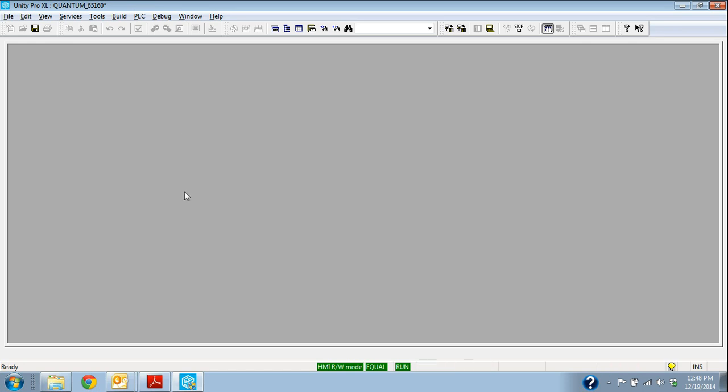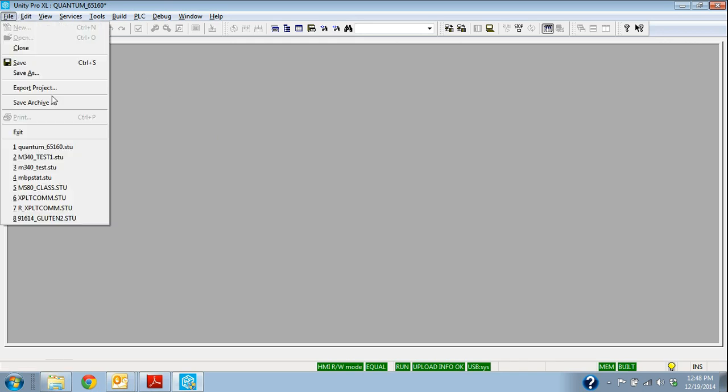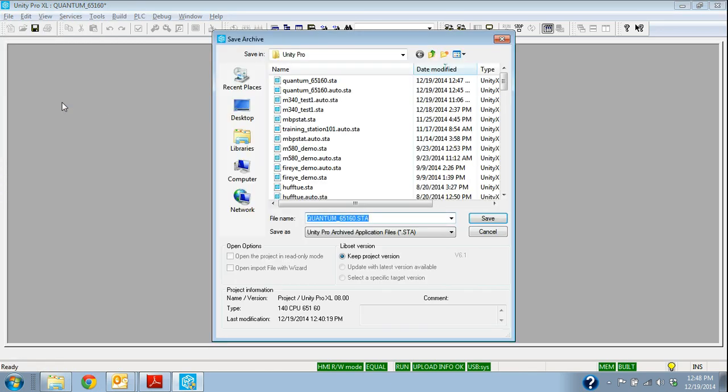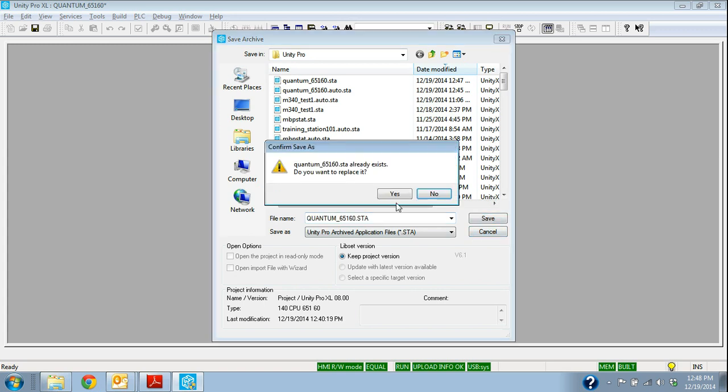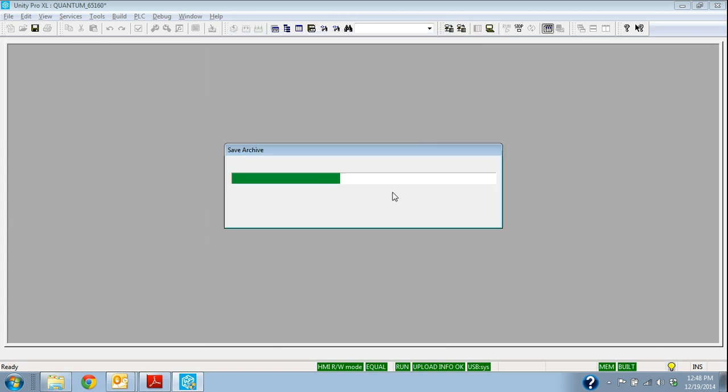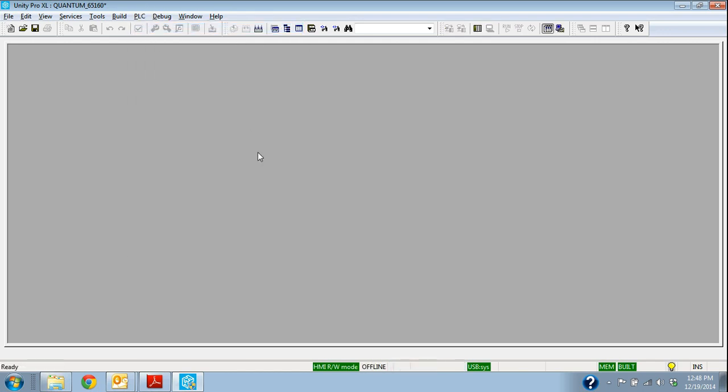We need to make sure that we have a current backup copy. In this case, we say the Quantum 65160. Open up the STA file. That's the archived file, and I said I was going to show you. In this case, if I want to save an archive, so whenever we back up, we want to save. It will automatically save it as an STA file, so we always know that we have a current backup, and the STA, the archive file, is the easy one that we can email around to somebody else or store on the corporate drive or whatever we need to do.